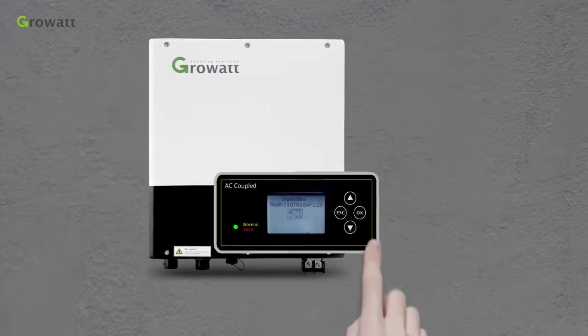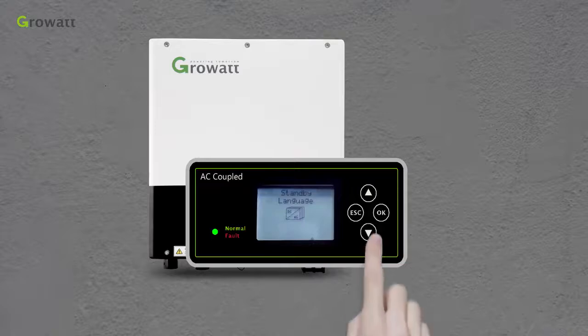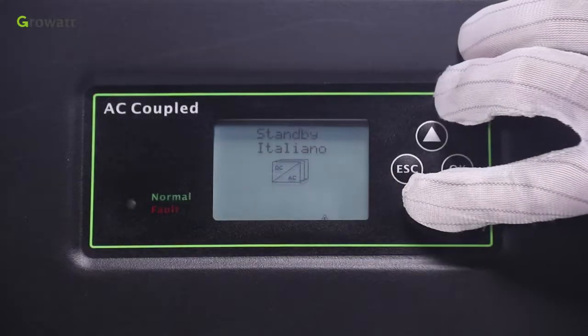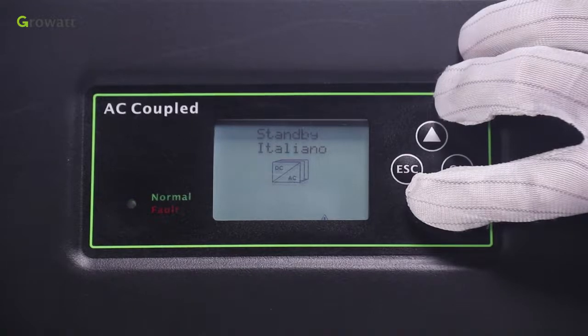From the LCD panel, we can change the mode manually, also including language, system time, lead acid cells charging voltage, default is 58V, discharge low voltage and so on.